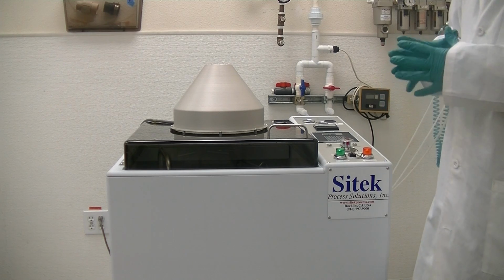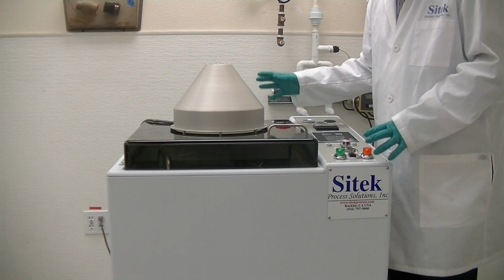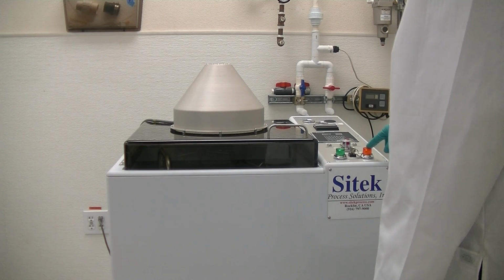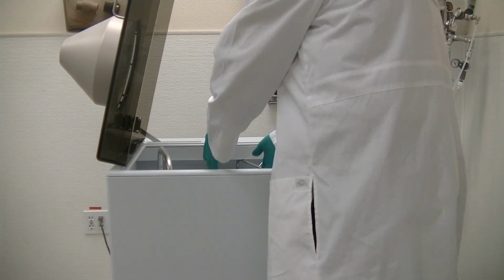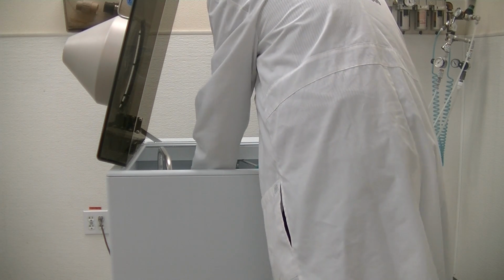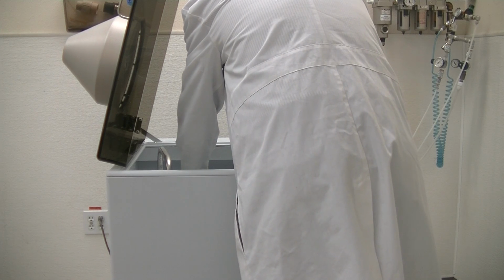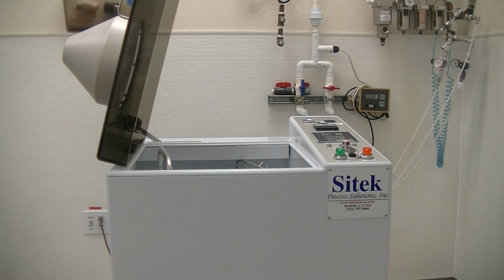That's the customer's choice. When the customer did the source inspection, they did complete training on the system. They know how the maintenance is, how the work's been done, and so forth. So, at the end of the process, all we do is simply say, open the hood. And you would just, which I can do here, most customers have a mask holding tool. And I'll just go ahead and take the mask out. In our case, it's a glass plate.